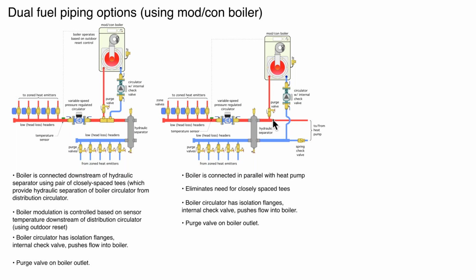This has the advantage that it allows, whether the heat is coming from the heat pump or from the boiler, it all goes through the hydraulic separator, which, remember, is also doing air separation at the top and dirt separation down at the bottom. When you connect that boiler up in either of these configurations, make sure you put a purge valve here so we can get the air dislodged out of that. And you do need a separate circulator to provide flow through the auxiliary boiler.